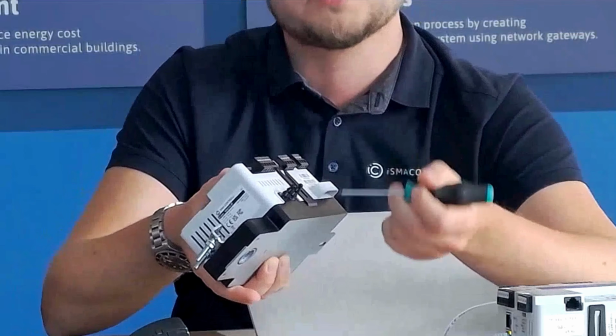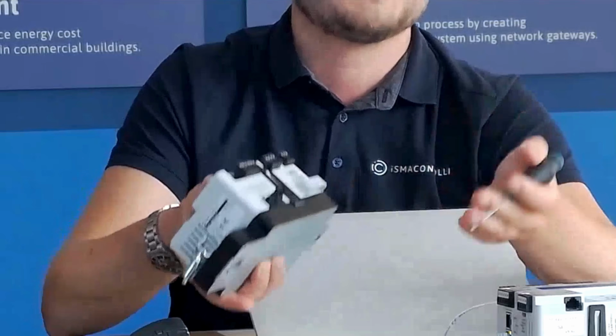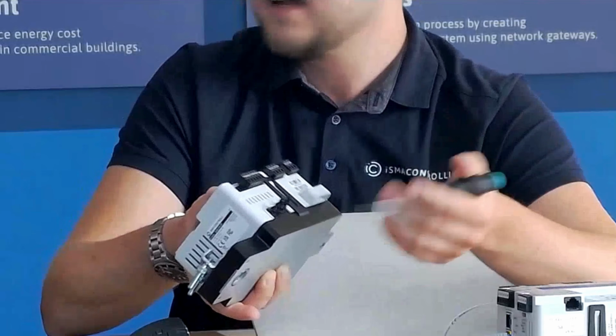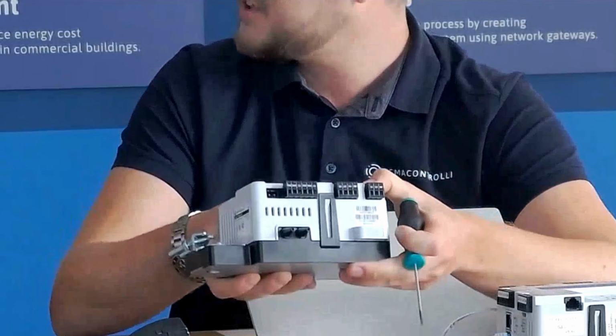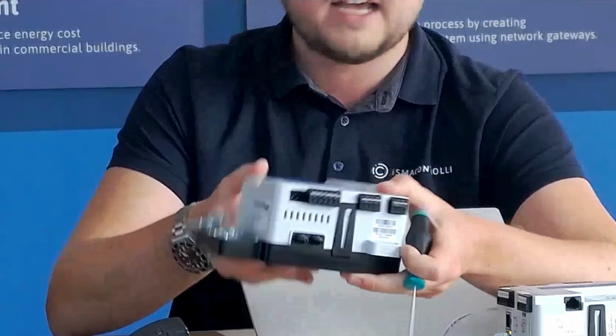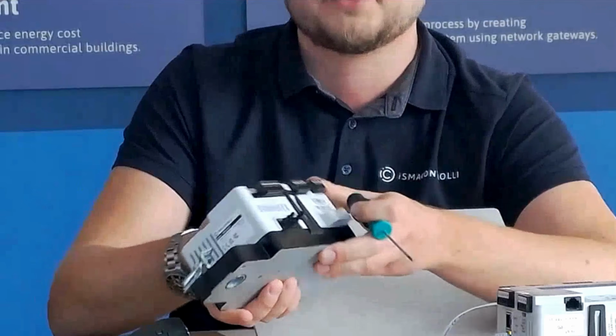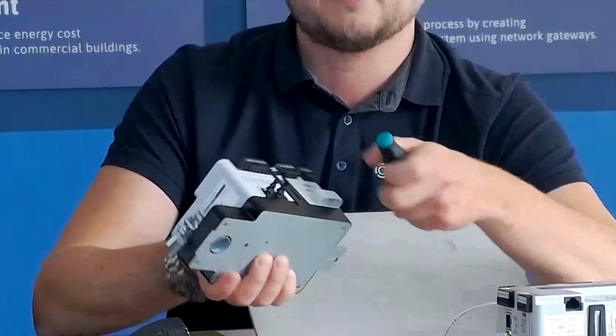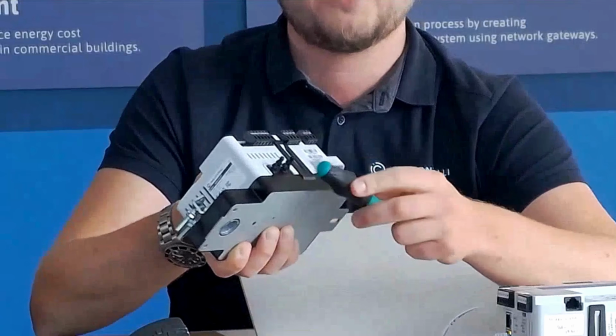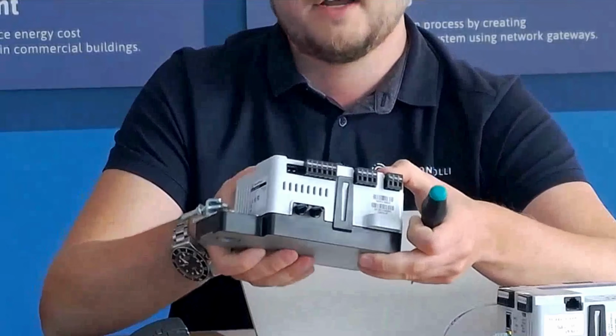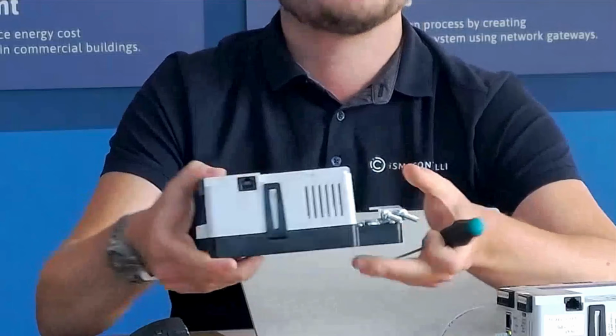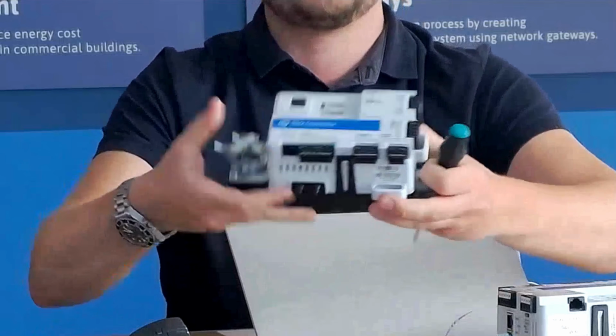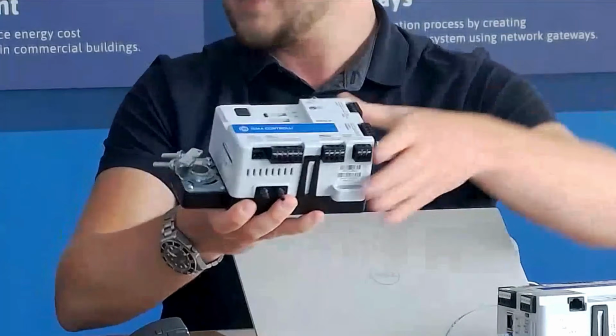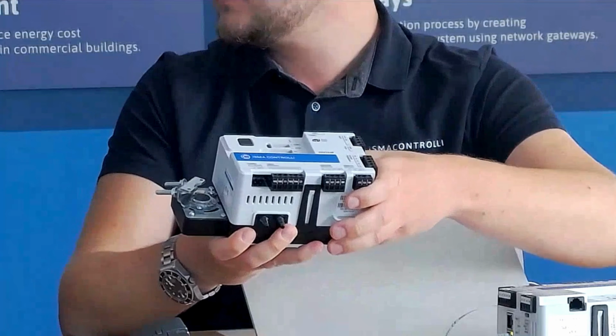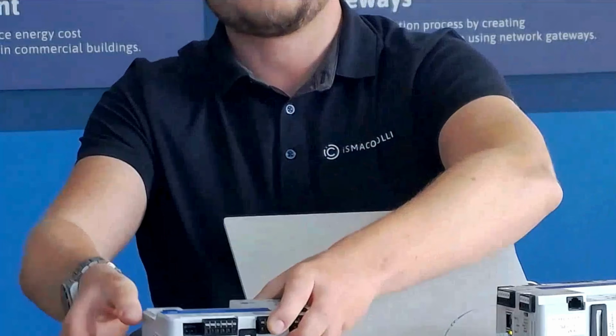We support daisy chaining also in the IO modules, but as it's in a control cabinet installation, there's no failsafe. But for such a unit, which you install under the ceiling, I think it's important that you have such a feature in the controller. And of course, last but not least, we also have the integrated pressure sensor right here. So overall, this is the controller as you see it. And I think now we can move to the tools, right? Yeah, let's take a look at the connected and powered, plugged-in controller.